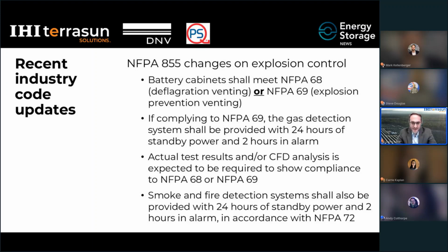NFPA noticed that, and a change was made, which is now permanent in the 2023 edition of NFPA 855. When complying with NFPA 69, a gas detection system now must be provided with 24 hours of standby power and 2 hours of power in an alarm state, whereas previously this type of backup power was not required. So this goes into the site design that both the integrator and developer need to consider, for how separate and independent standby power will be provided. When meeting either NFPA 68 or 69 requirements, actual testing and/or CFD analysis will be necessary to prove to a local authority having jurisdiction that your product meets the requirements.